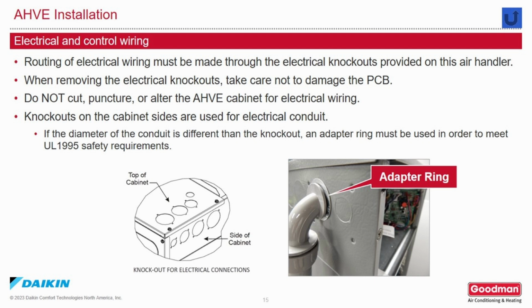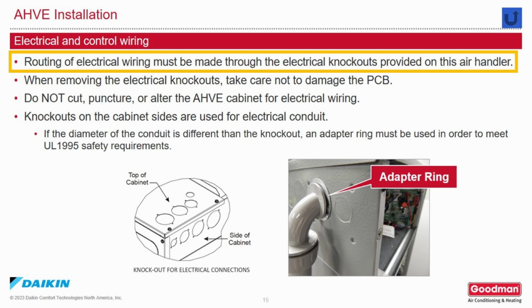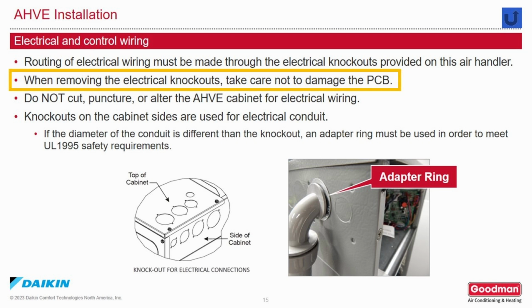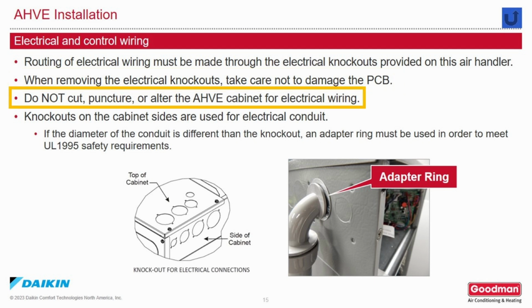Electrical and control wiring. Routing of electrical wires must be made through the electrical knockouts provided on this air handler. When removing the electrical knockouts, be careful not to damage the circuit board. Do not cut, puncture, or alter the AHVE cabinet for electrical wiring.